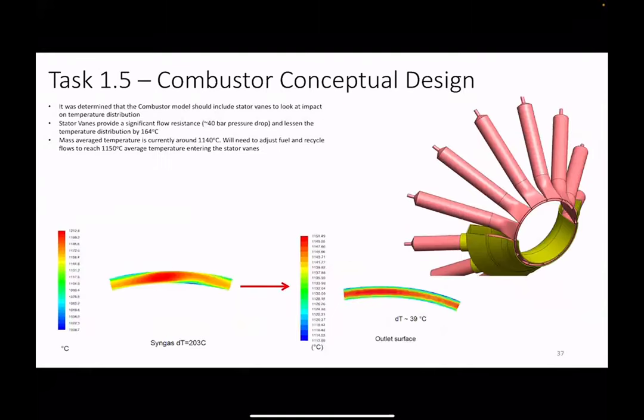Most likely, our final design will look something like this, with individual combustor cans and transition pieces for each can, rather than a general plenum. This lets us tune the flow better, moving from decelerating flow to constant acceleration with increasing velocity, giving more uniform temperatures into the turbine first stage vane. Because of the horizontally split line design we're developing, there will need to be changes in the combustor can and transition piece geometry at the split lines. By making them individual, we can adjust each can to give uniform flow distribution into the turbine.